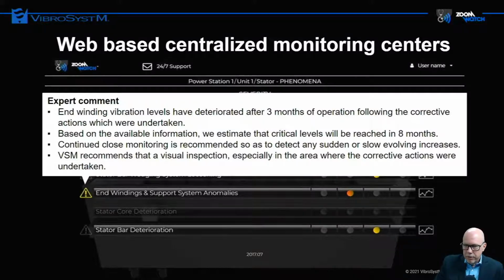When you do have an issue, there's an expert comment that will tell you why the value is what it is. For example, end winding vibration levels have deteriorated after 3 months of operation following corrective actions that were undertaken. Based on the available information, we estimate critical levels will be reached in approximately 8 months. So we recommend continued close monitoring to detect any sudden or slow evolving increases, and we recommend a visual inspection, especially in the area where the corrective actions were undertaken.